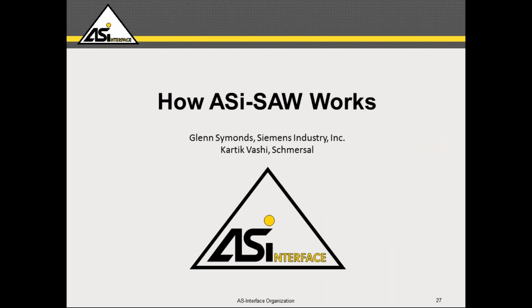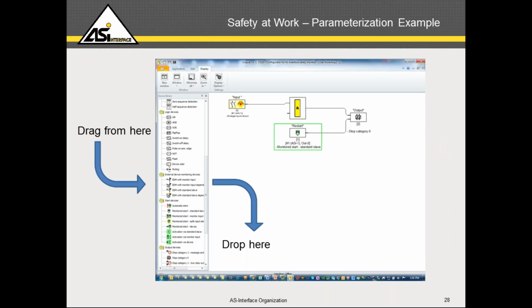So how does the ASi-SAW work? How does this scheme work? Well, the ASi-SAW functions are parameterized in the safety monitor, and the way that's done is using a software called ASIMON. In this software, you simply drag components and functions from the library you see there on the left into the window on the right, connect them together in the control scheme you want, and then download that to the safety monitor. That's it. Then away you go. It's really, really simple, and it's as easy as it looks here.